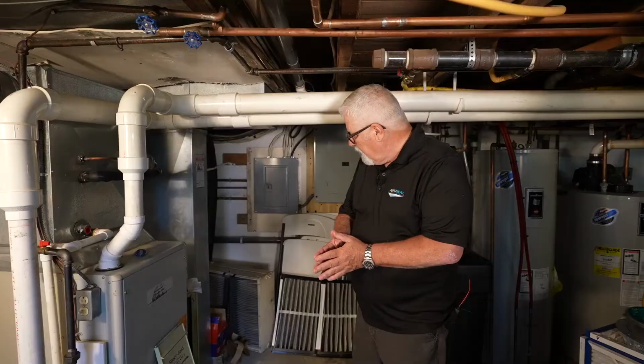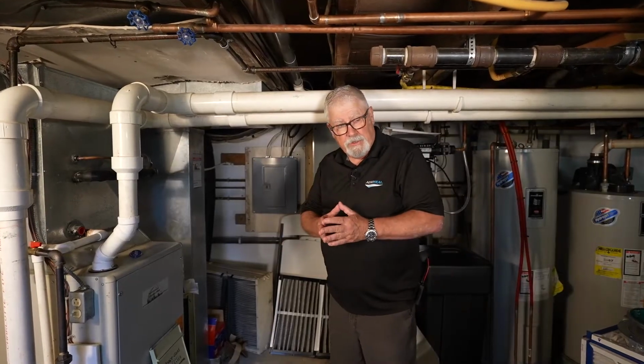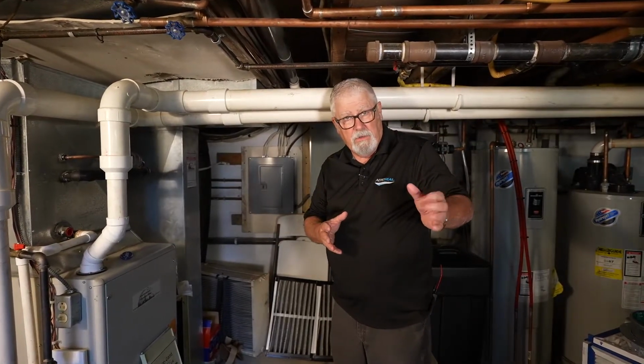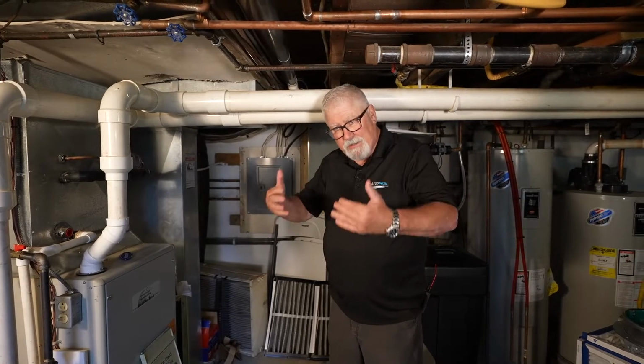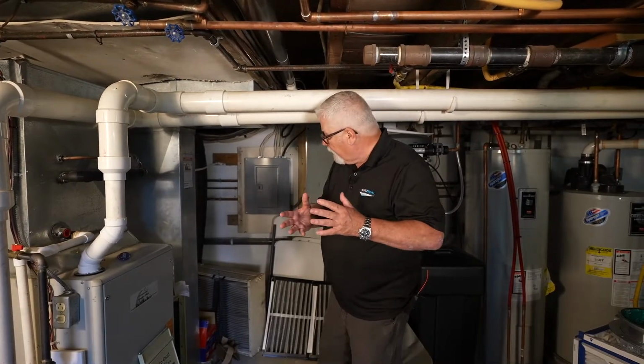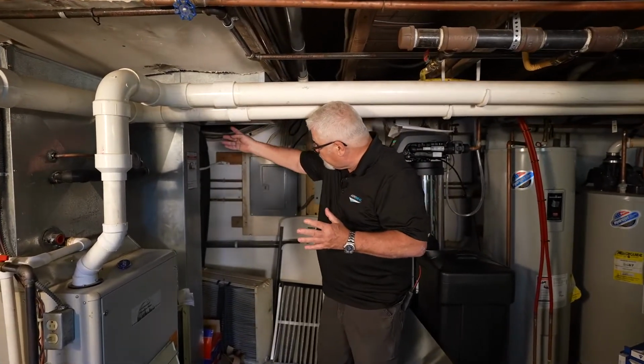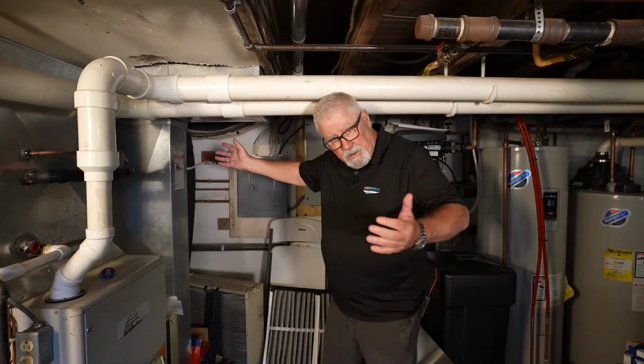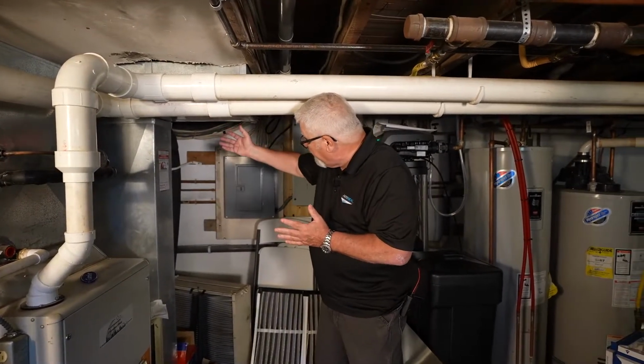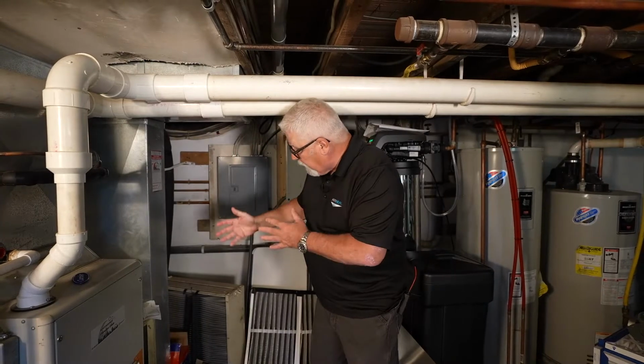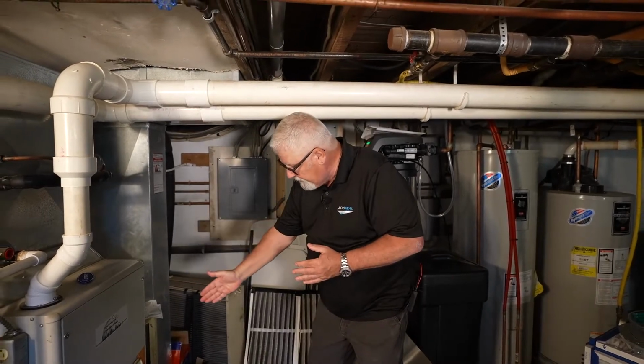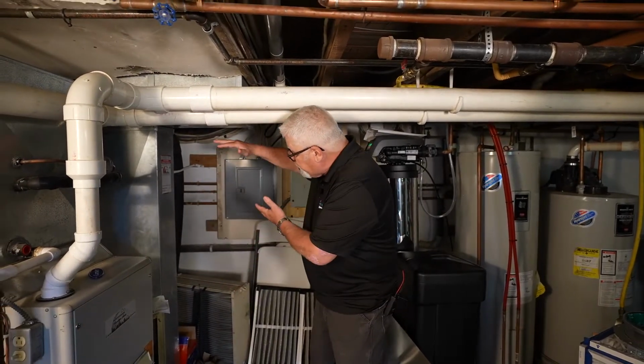All right, so to get started, what we're going to do today is use my fan box just as a way to push air. I'm going to try to figure out what's going on, so I'll hook up my lay flat. I've got an injection point we're going to cut in right here, so we'll have lay flat coming from my fan box to this injection point. We'll block everything off at the furnace so that we can pressurize the return.